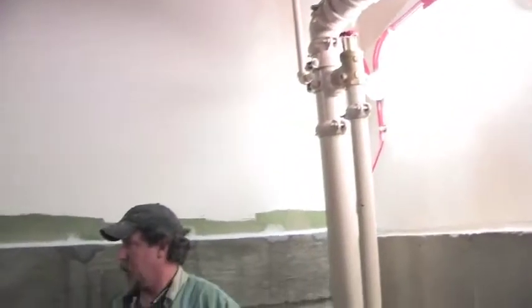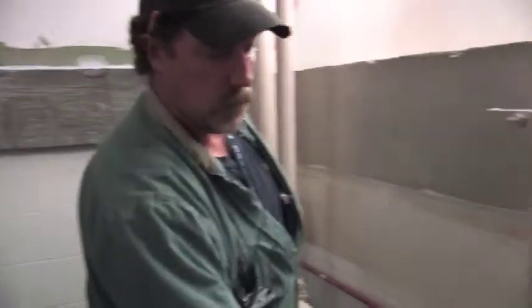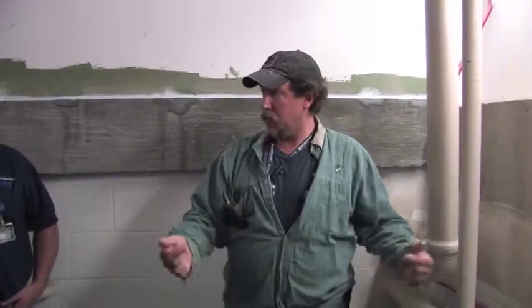So if you got an issue upstairs on the high side, you close this valve and the one over there, and it's going to stop everything from 8 up. Is that what you said, a 6 up? Yeah. Say you wanted to isolate the high riser. Right. That'd be this one right here. And you actually put an H on it, but it's on the tags here. If you wanted to just work off of this riser here, from 6 through 12, you could just shut this off here. But there's also floor control valves on every floor. So you got to close it off up there.